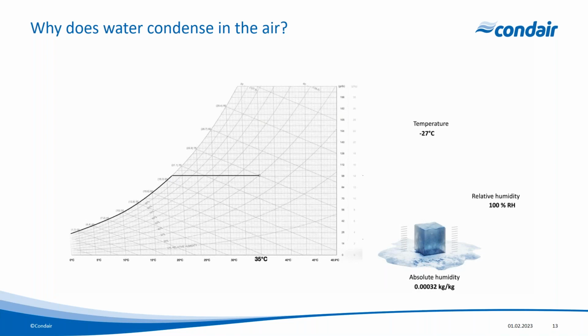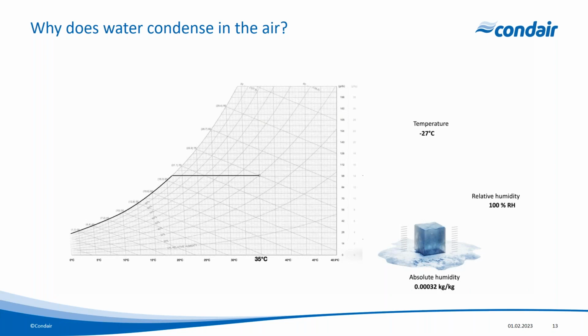And again, because the air is being circulated by the evaporator fan, the evaporator is typically the first place that moisture will settle on. So we've contracted that air and cooled it right down to, let's say, minus 27 degrees C. Relative humidity is still at 100%, but now my absolute humidity or absolute moisture content is 0.00032 kilograms per kilogram. So I've released all of that moisture into the freezer store, and that is going to, because it's below zero, form ice inside your freezer.